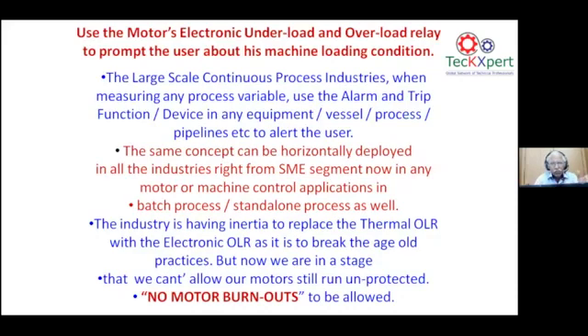All the large scale process industries have gone for this alert and trip mechanism and they are using it. But small MSMEs have not tried this. Let us not go for any big amount of IoT or high-cost traditional or digital solutions. The existing relay can be set with an underload and overload, and we can see whether the motor is operated in the right loading range. This is more important. Let us see to it that we do not have any motor burnouts in the industry. As and when motor burnouts happen, the losses in the motor accumulate more.